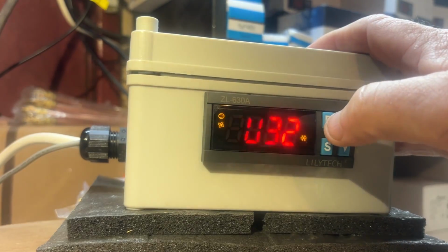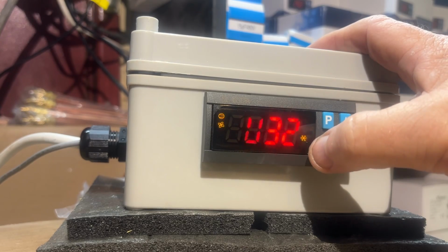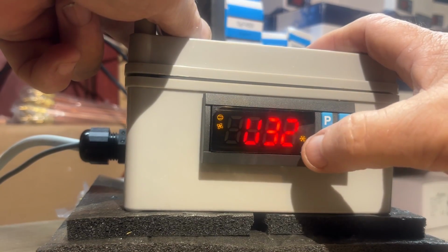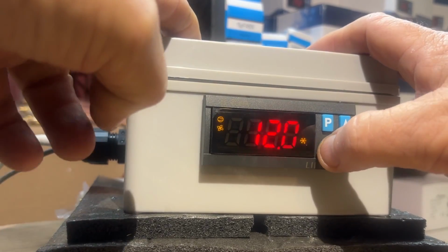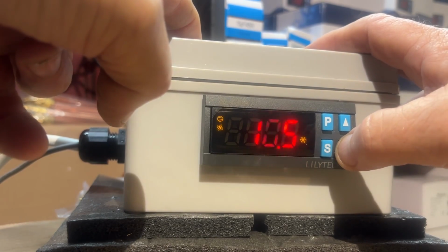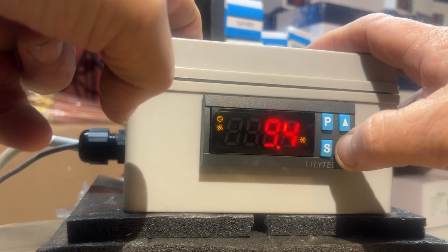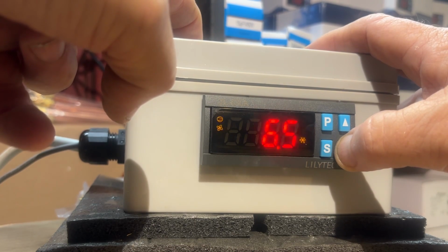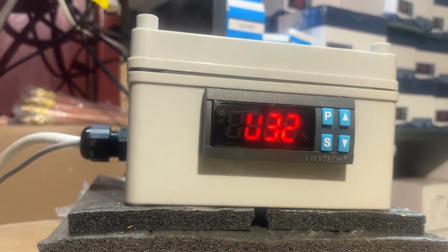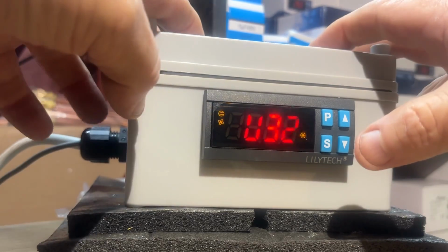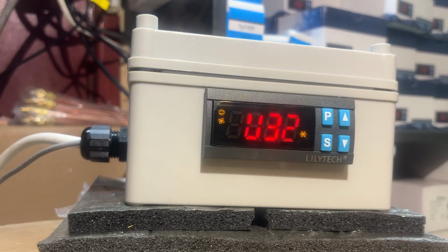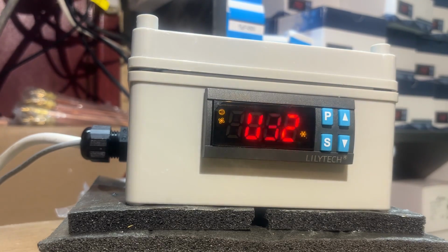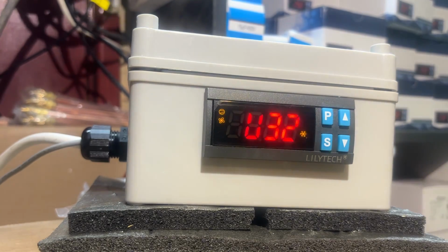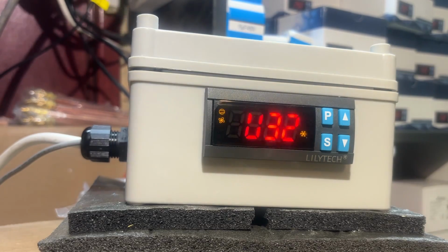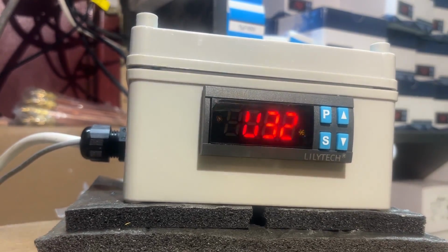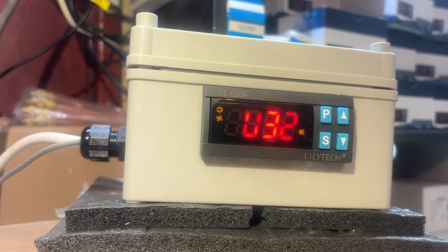Okay. And then 32 is the defrost temperature, so the defrost cutout. The temperature that the defrost probe reads in the evaporator, we want that at 5 degrees. So if the defrost coil is warmer than 5 degrees, it won't defrost. So this way, you always guarantee that the evaporator is clear of ice. So it comes on the defrost every 2 hours for 15 minutes. If the defrost coil is warmer than 5 degrees, it won't defrost. It'll just keep on doing its normal thing. It knows it doesn't need a defrost. And of course, there's no defrost heaters. It's just fan defrost.